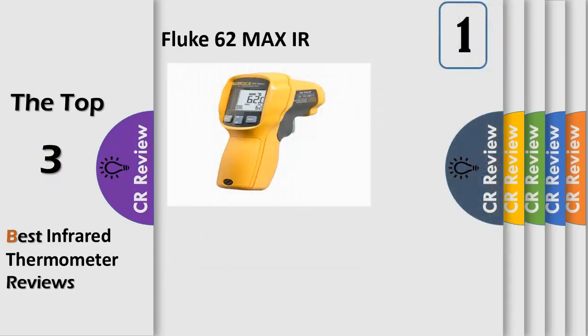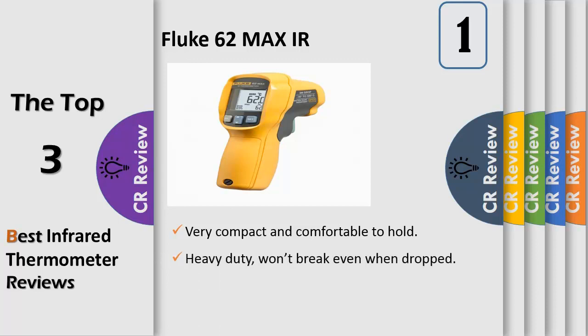Number 1. Infrared thermometer for non-contact surface temperature measurement, for use in monitoring electrical, mechanical, HVAC, and automotive systems. Measures temperature from minus 30 to 500°C (minus 22 to 932°F), with an accuracy of plus or minus 1.5°C or 1.5% of the reading from 0 to 500°C.